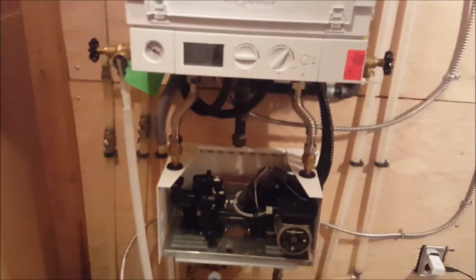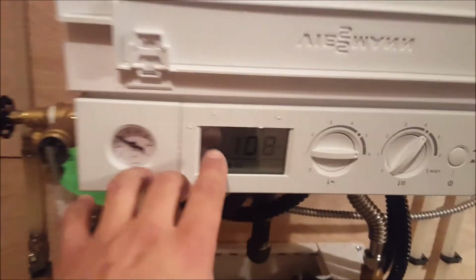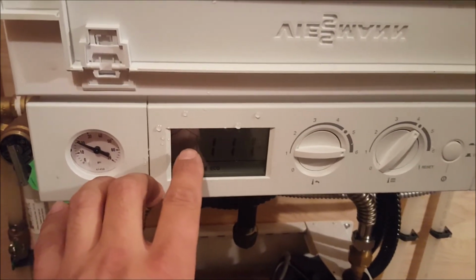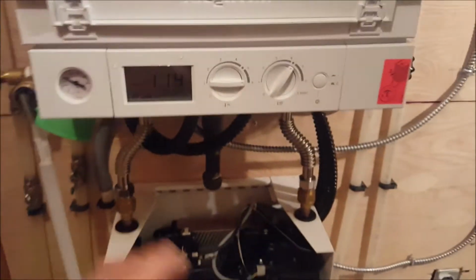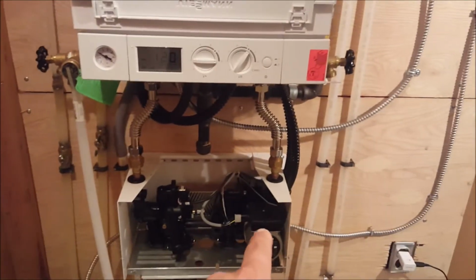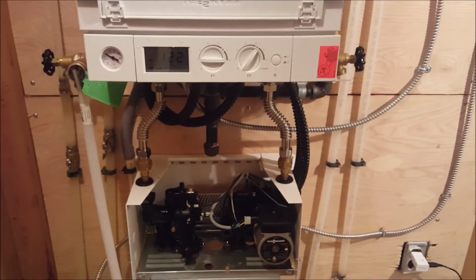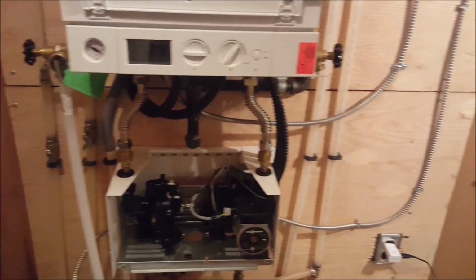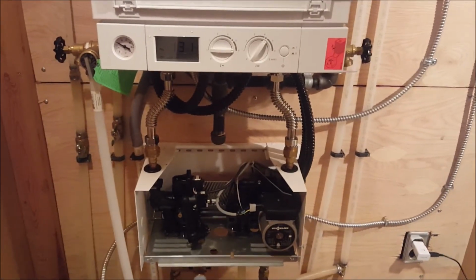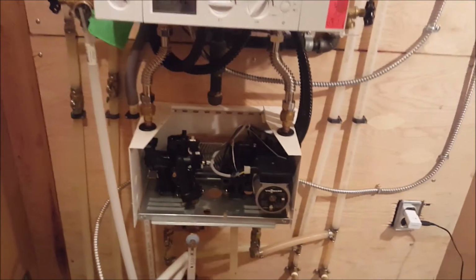So if you have one of these units and you're getting a tap here, or the picture of the rad, and you know you're not getting any, the boiler itself isn't firing up, it could very well be that pump. It could also be a pressure switch or a control board, located up in this unit. But the first thing you'll want to check for sure is that you're actually getting circulation with this pump.